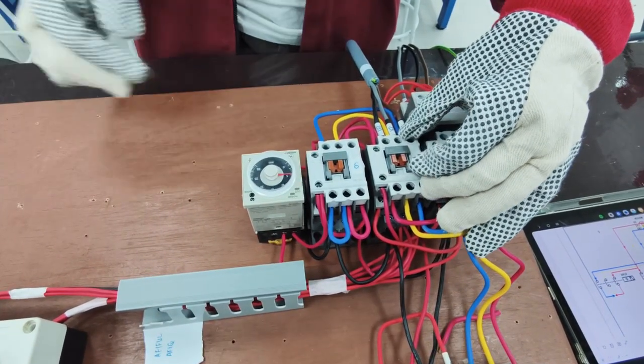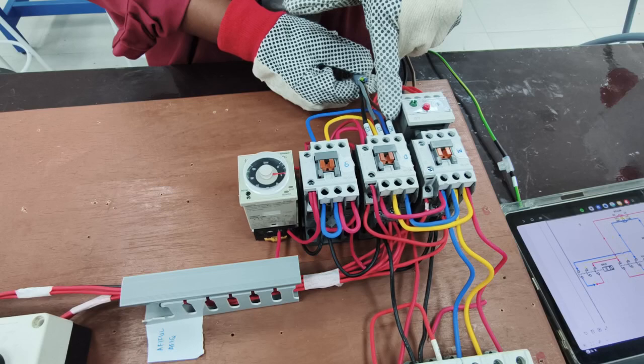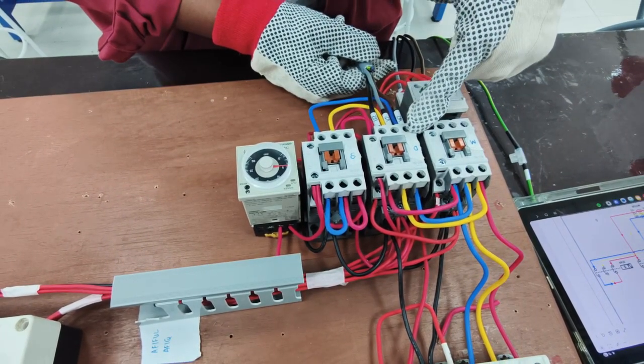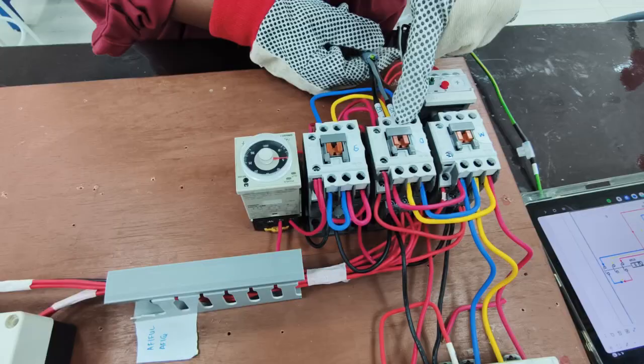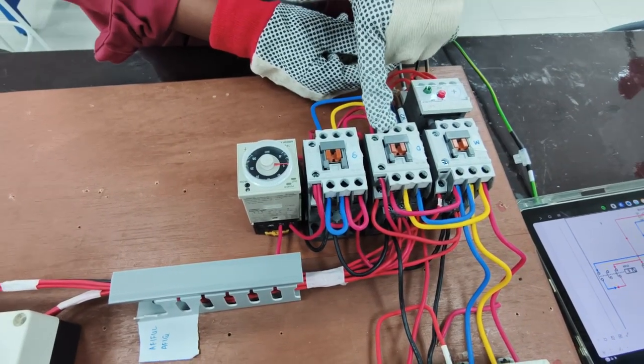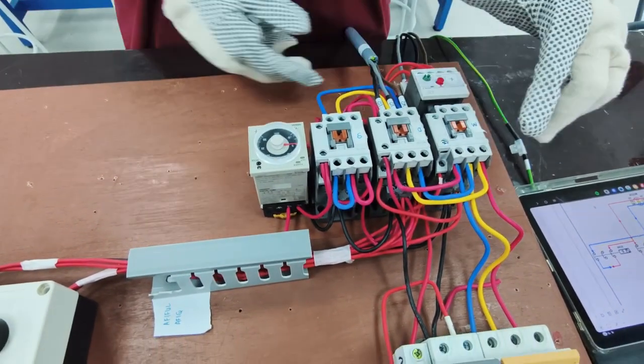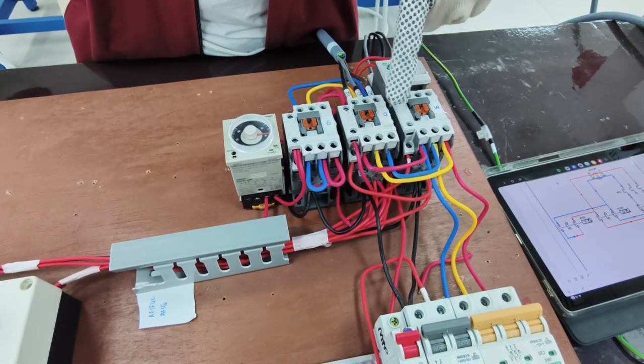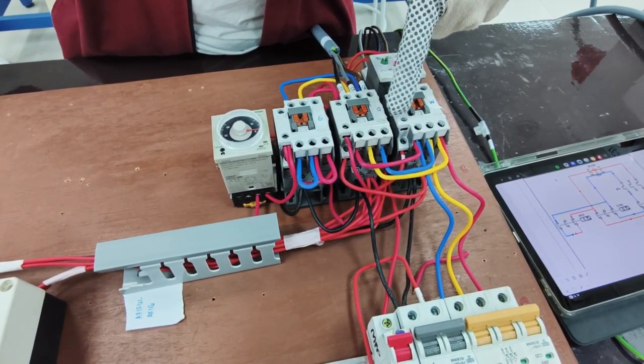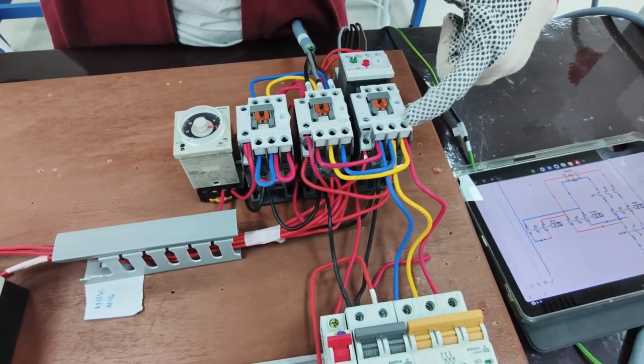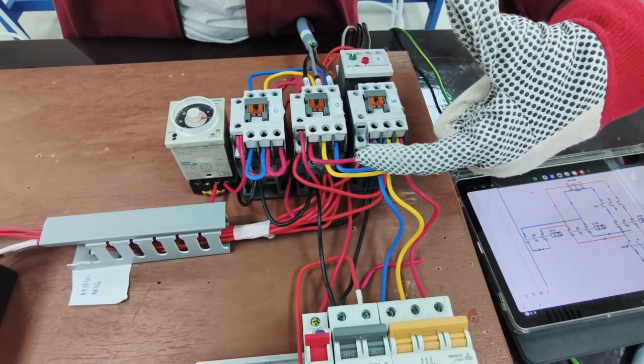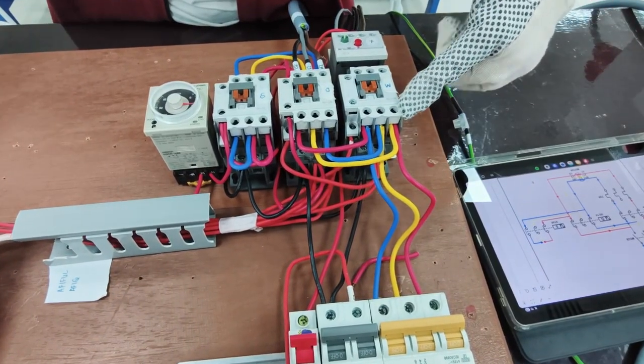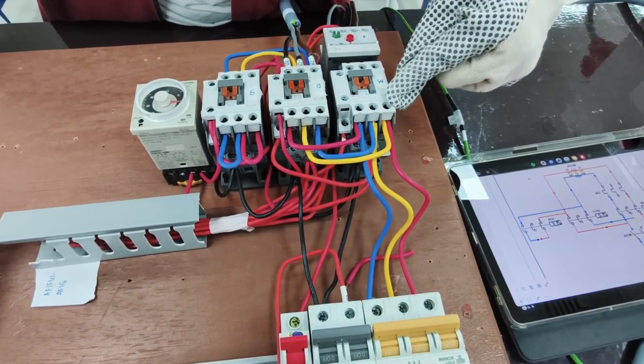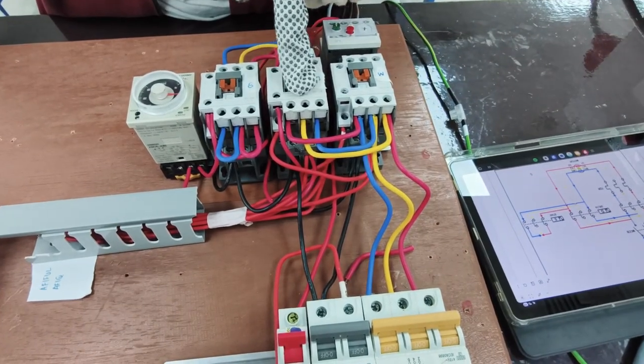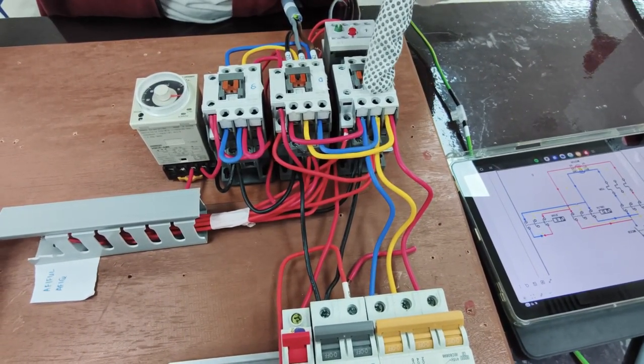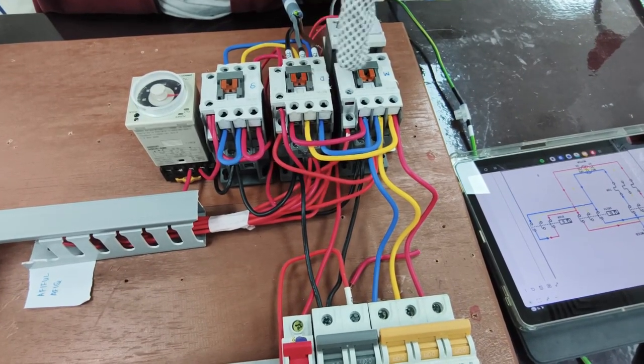So from the delta, from the motor, it will go for W2, will go for U, and V will go to V, and U will go to W. And with that, after that, our main contactor will loop to our delta contactor. But it will be a bit different, because our R will go to our S, while S will go to the R, and lastly our T will go to the same T.